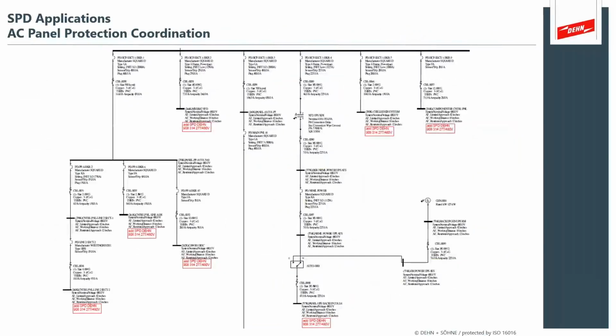What does it look like at a more complicated load center? You'll have your mains inputs. You'll have the expectation to put a larger surge protection at the front of the building, where you have the likelihood of ground potential rise, and then you have a smaller SPD coordinated with it downstream after you enter the distribution system. Perhaps it's on the downstream side of the backup generator.